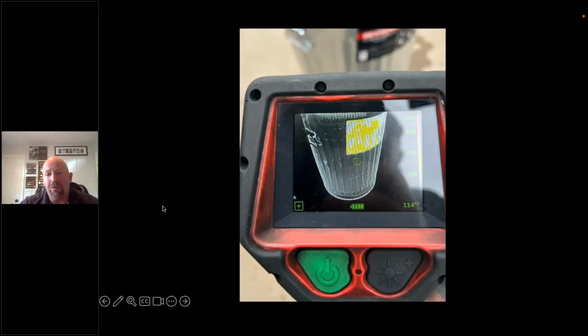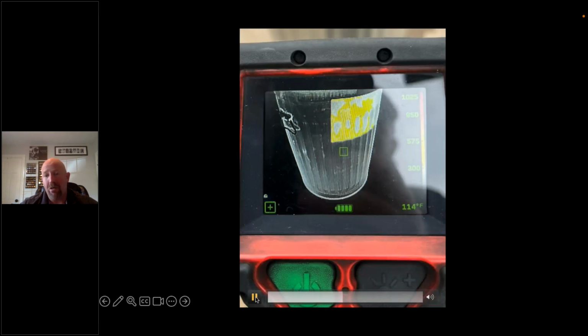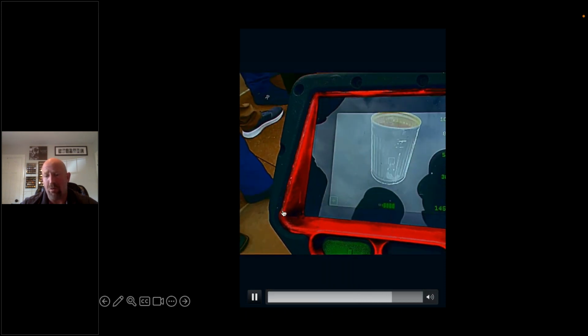This is a simple demonstration that we often do with the Max Firebox, because the side of it has diamond plating. Well, we use metal trash cans when we're done with our burns because we need somewhere to put the embers. We bought this little $12 metal trash can from a home improvement store. It still had the sticker on the side. Well, when I pressed play, the spot temperature says the side of that metal trash can is 114 degrees. It's clearly hotter than that, because the shiny surface is reflecting energy back. And it's a low emissivity object, which means it reflects a lot of energy. High emissivity object absorbs or transmits energy pretty well.